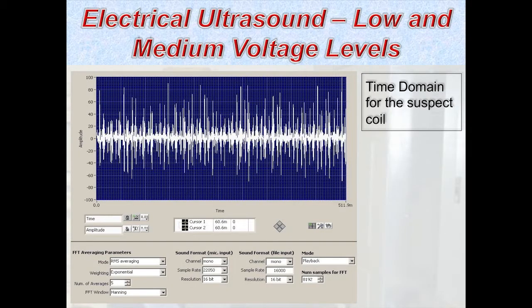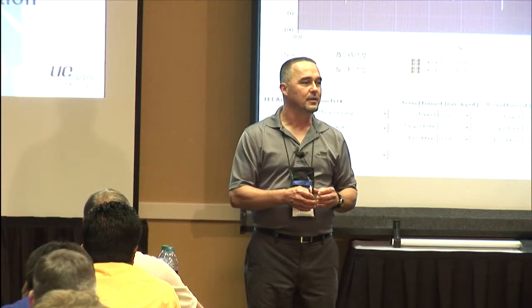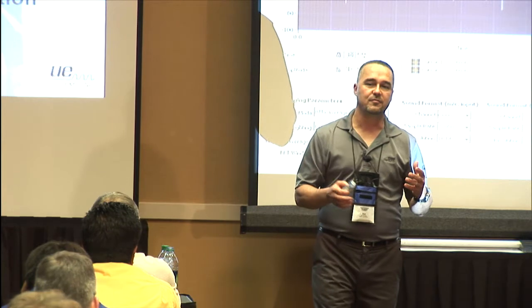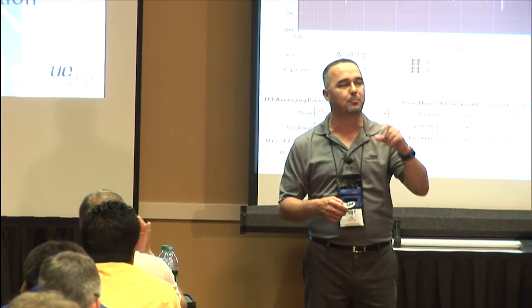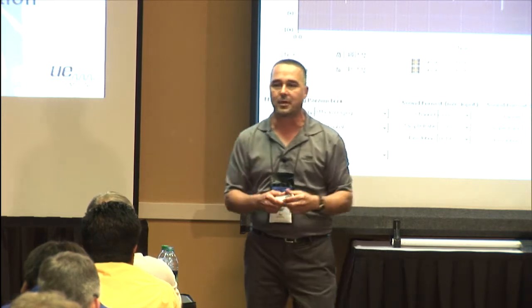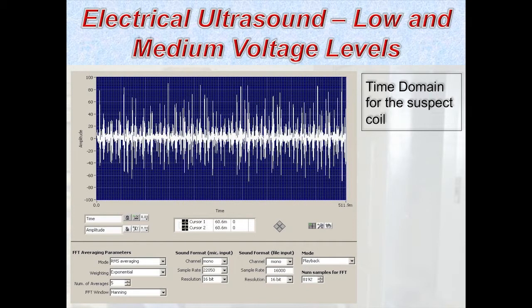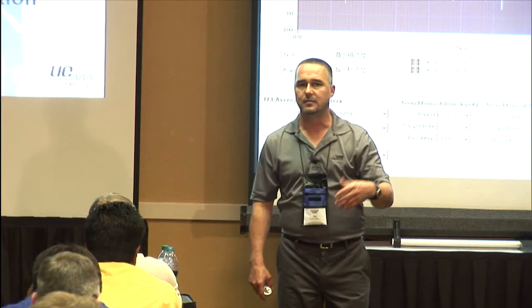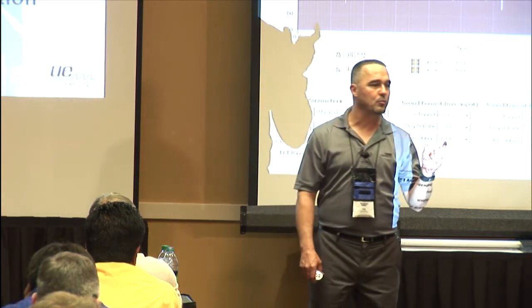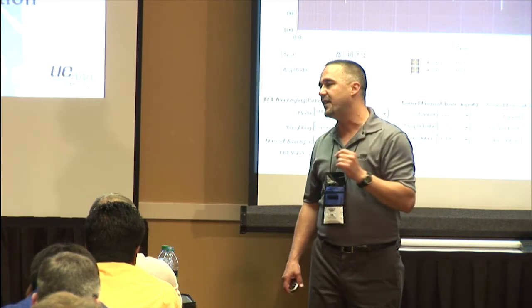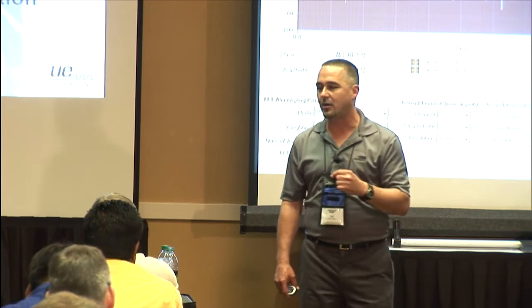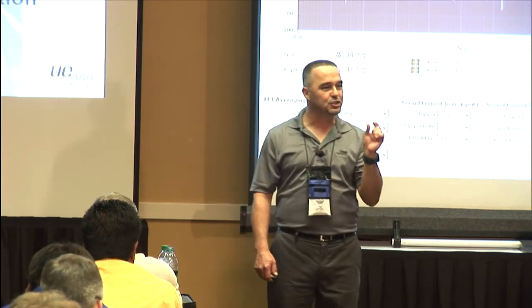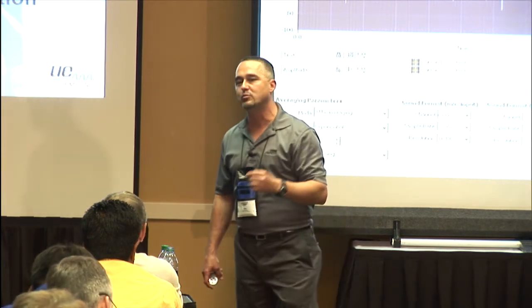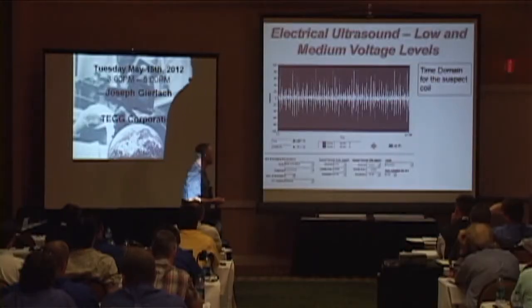Looking at the time domain, this could be tricky because it has a footprint of a tracking anomaly. We characterize it by variation throughout the recording in the amplitude of these excursions from the center line, and also differences in the spacing, meaning time. If you relate tracking to an electrical sine wave, on a 60 hertz system one electrical cycle is a very predictable, repeatable time base of 16 milliseconds. But discharges of energy along insulators have no pattern relative to the sine wave, so the timing changes with a tracking event. It's not like that with some other events, but with tracking it is, so you'll see differences there.